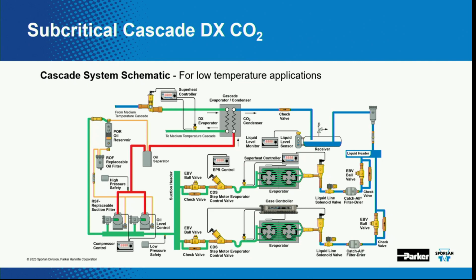Because with transcritical, you are using what's called the gas cooler. You're blowing fans across the coil, right? So it's like, oh, that looks like what I'm used to. But the interesting thing is that it's not actually doing what you're used to it doing. And that's why they don't call it a condenser, because you're not condensing. You're just cooling. Yeah, we're cooling in this case.